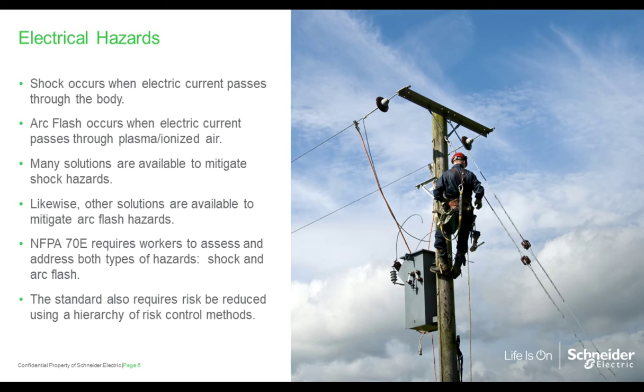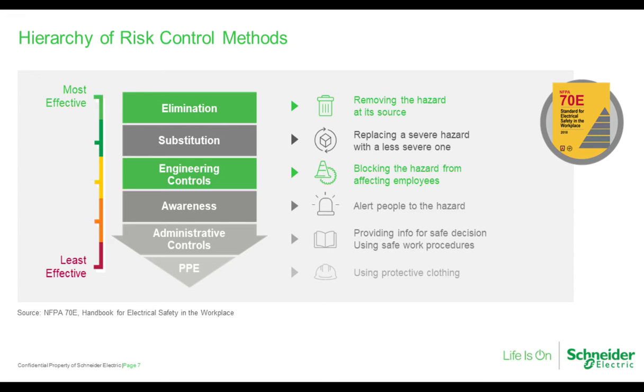And the 70E standard requires workers to reduce risk using a hierarchy of risk control methods. As you can see on the graphic here, there are 6 types of risk control methods. The methods are arranged in order from more effective at the top to less effective at the bottom. Those that appear at the top of the list are called higher order controls. At the very top of this list is elimination. And in the context of 70E, elimination is accomplished by establishing an electrically safe work condition.